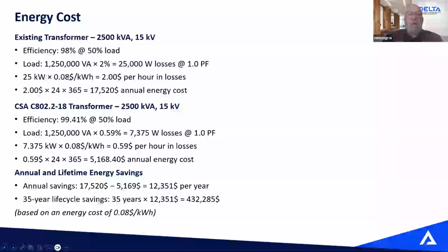I use the kilowatt cost of Quebec. I know we're lucky. So if you pay only 8 cents per kilowatt, 25 kilowatts times 8 cents, you have $2 per hour in losses, per day, per year. So your cost of energy is about $17,500 per year. Cost of energy, losses burnt in the transformer that you lost. You don't use them, but you pay for that.